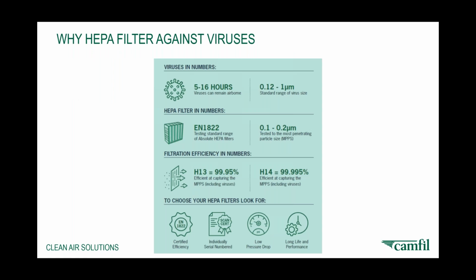Why HEPA? Well, we're saying that viruses can remain airborne for between 5 and 16 hours, depending on the room, on the airflow design, etc. The HVAC system, the lack of a HVAC system, there are various reasons. And these standard viruses tend to be in the range of 0.12 to 1 micron.